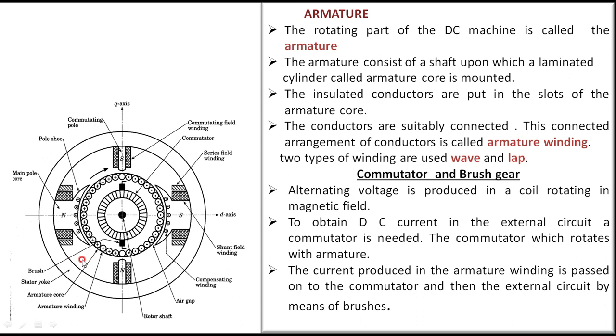The armature is the rotating part. In the case of the DC generator it consists of armature conductors placed in the slots of the outer periphery of the rotor. Both the armature and the stator are made up of laminations to reduce iron losses in the machine. The conductors are put in the slots of the armature core and connected in a particular fashion — either wave winding or lap winding.